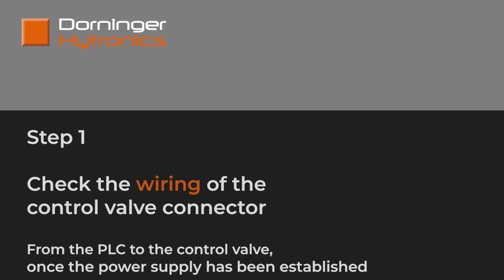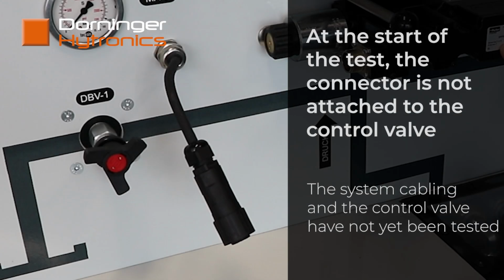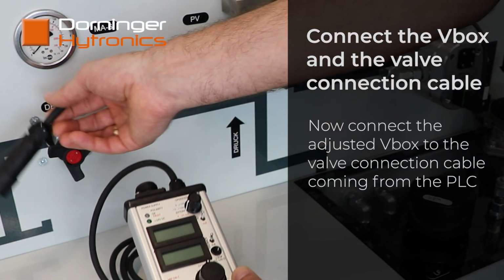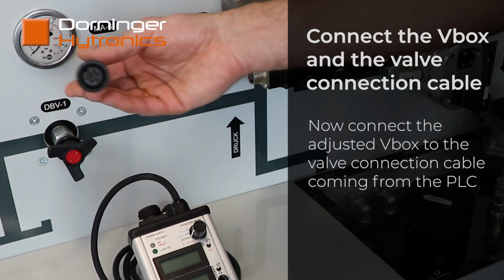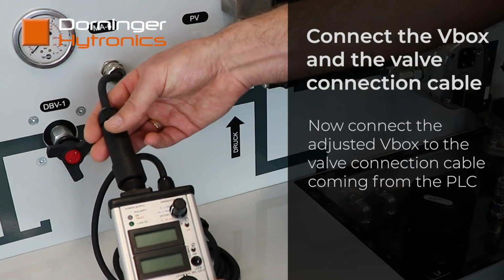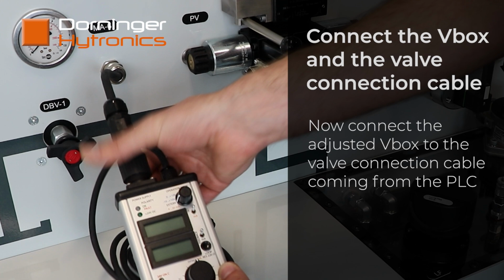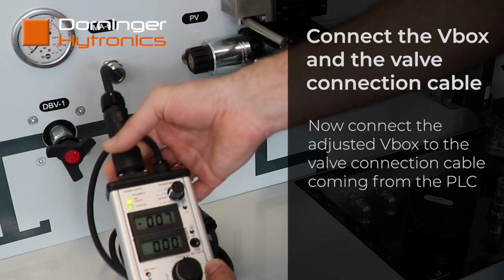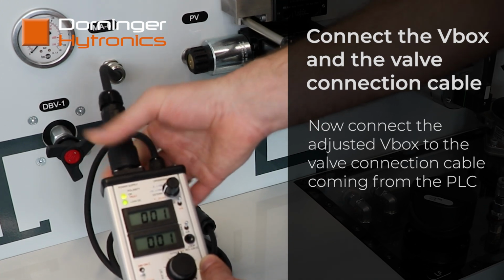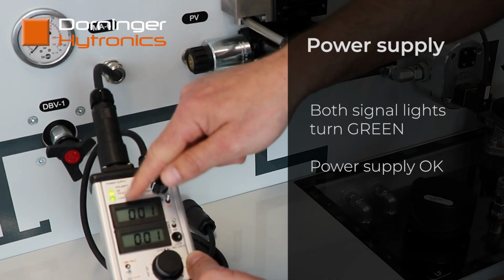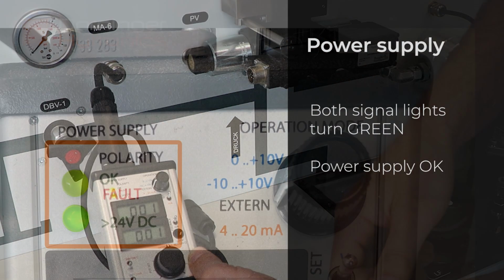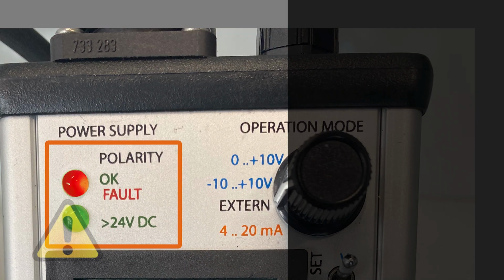To do this, the correctly configured Vbox is initially connected only to the valve connection cable. This cable comes from the PLC or the machine control system. This allows us to check the power supply directly at the valve connection cable. Important, both power supply indicators must light up green. The correct polarity must also be observed. Incorrect polarity can cause malfunctions or damage the control valve electronics.